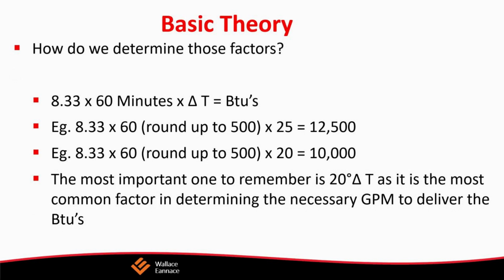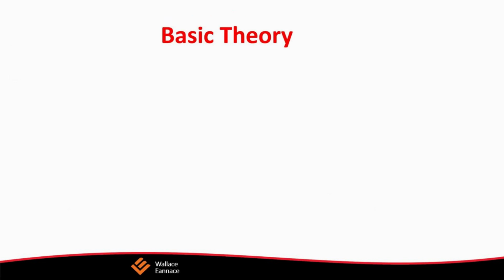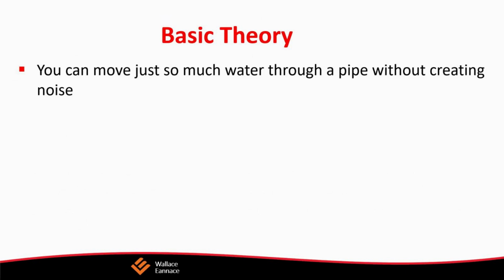Now, if you think about that, we can also work that backwards. If we have 300,000 BTUs, and 20 times 500 is 10,000, so we divide by 10,000, we would get 30 GPM. The point being that if I have a 300,000 BTU boiler, I need to flow about 30 gallons per minute in order to get a 20-degree delta T. So 10,000 is the factor that is consistent with a 20-degree delta T, which is most common and is what is used in traditional heating systems.